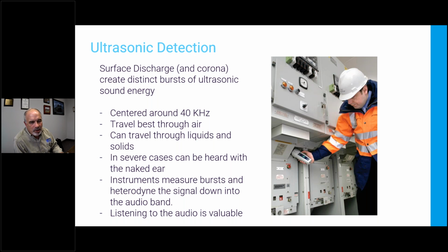What the instruments do is they'll detect these bursts, they'll measure them, they may provide phase result plots, they may provide various different characteristics for the user, but almost all of them also take the signal and, by a process called heterodyning, drop the signal center frequency down into the audio band. And what's nice is it doesn't change the nature of the audio, and I can listen to it. And your ears are incredibly sensitive and incredibly discriminatory. You can hear the same singer sing the same song on 2 different albums, and you can tell the difference. It's hard to get a computer to do that. So listening is always going to be valuable, and if you're not doing that, you're not doing ultrasonic testing.